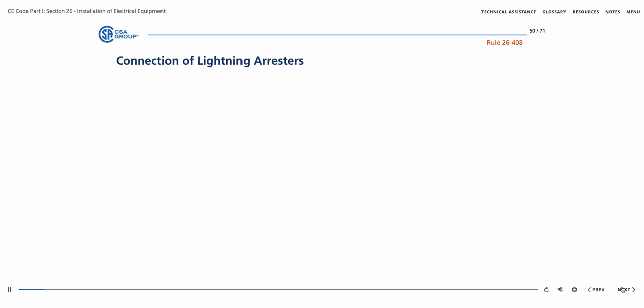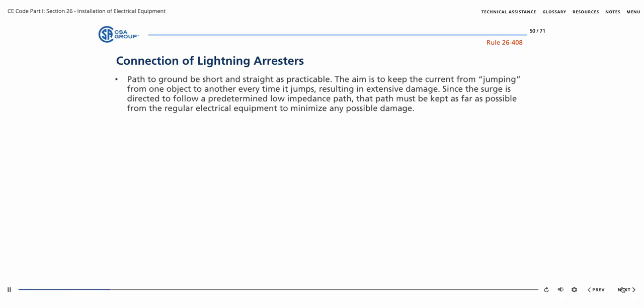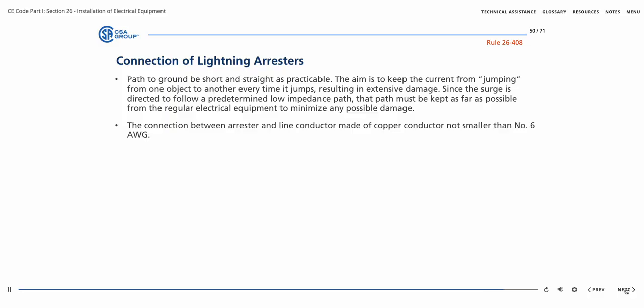Due to the high voltages involved, Rule 26-408 requires that the path to ground is to be as short and straight as practicable. The aim is to keep the current from jumping from one object to another, since every time it jumps, it results in extensive damage. Since the surge is directed to follow a predetermined low impedance path, that path is to be kept as far as possible from the regular electrical equipment to minimize any possible damage. The lightning arrester is also to be connected by, at a minimum, a number 6 AWG copper conductor.